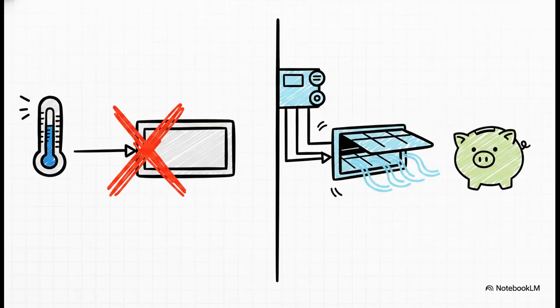So the huge takeaway here is this. If you are running a simple dry bulb strategy, the computer would see 77 outside and 75 inside, and it would flat out reject the outdoor air because it thinks it's too warm. It would make the wrong choice. But in enthalpy-based control, it sees that bringing in that 77-degree air actually takes far less energy for the mechanical system to cool down. It accepts the air, saving you massive amounts of energy. And honestly, this specific scenario happens all the time in dry or semi-arid climates.